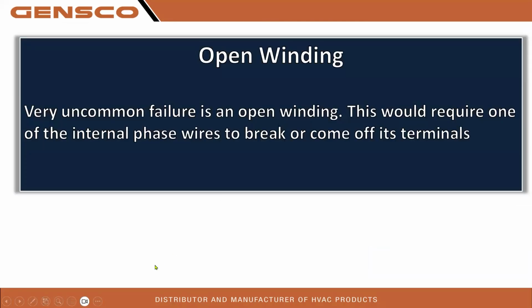Now, another failure would be an open winding. This is a very uncommon failure. This would require one of those internal phase wires to break or come off of its terminals. Remember the photograph that showed the good winding and all the wires that connect it? This would be one reason why you may have an open winding. One of those wires is actually burned off or broken.